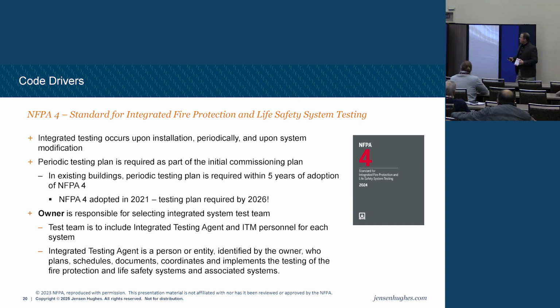The periodic testing plan is required as part of the initial commissioning. So again, that's a fully documented procedure you're going to follow, and it gets maintained with the records. For the NFPA 4 2021 edition, the testing plan is required for 2026 because the periodic testing plan is required within a 5-year adoption of NFPA 4, right?